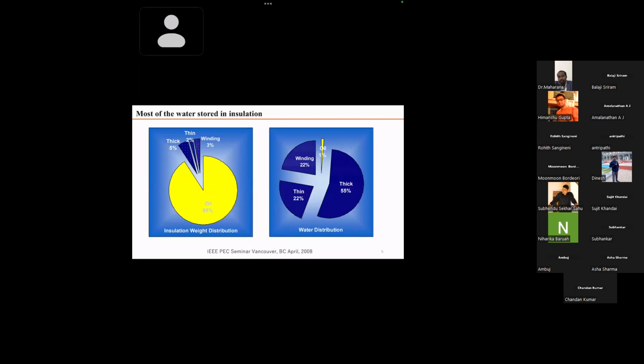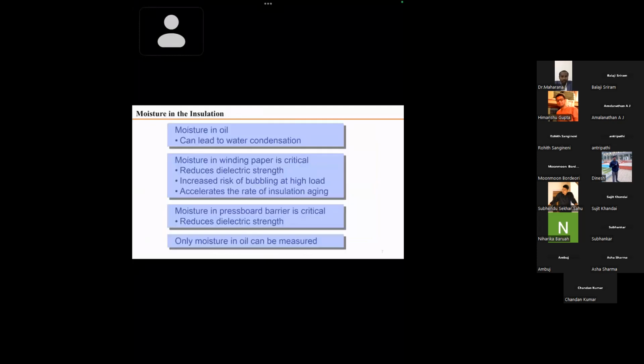That is why we generally measure the moisture in the oil. Moisture in oil can lead to water condensation. Moisture in the winding paper is critical because it reduces the dielectric strength, as we all know, increases the risk of bubbling at high load, and accelerates the rate of insulation aging.